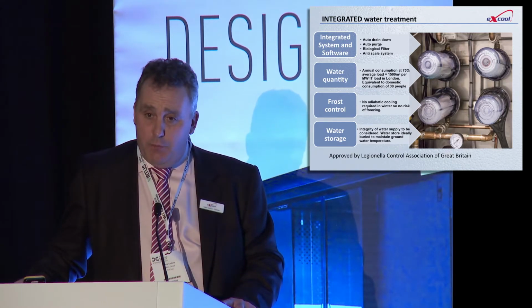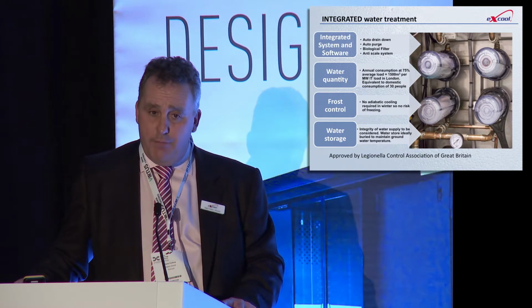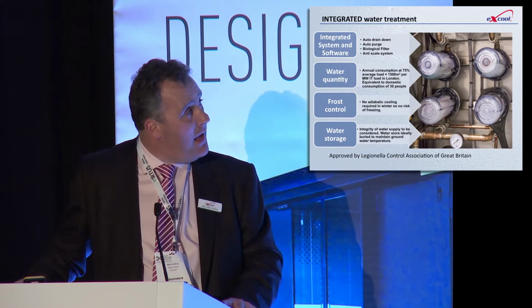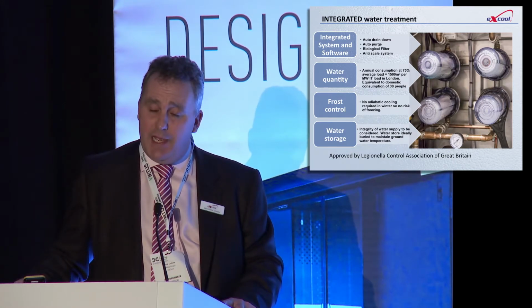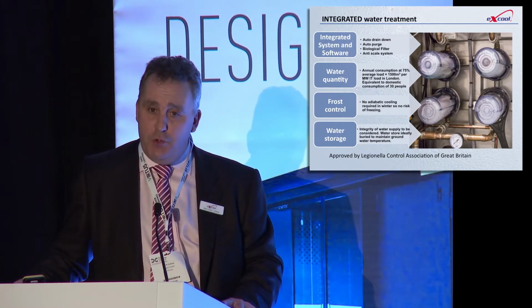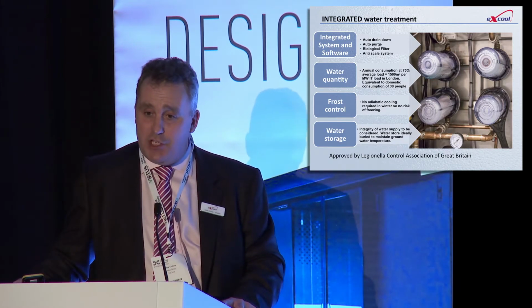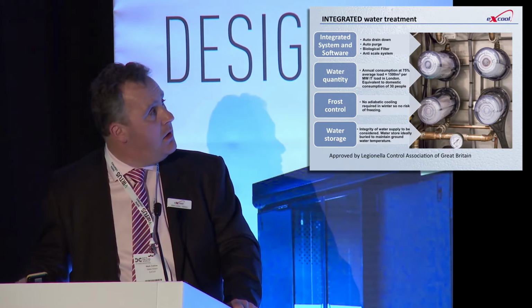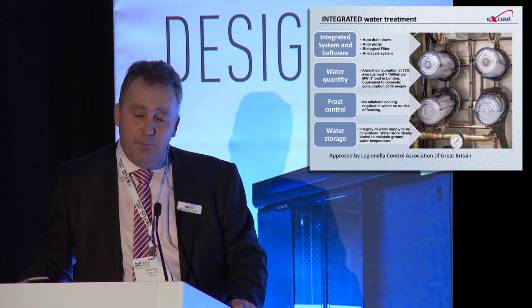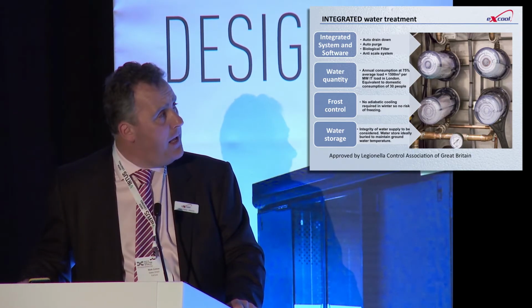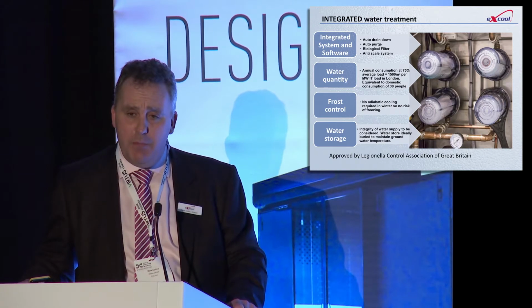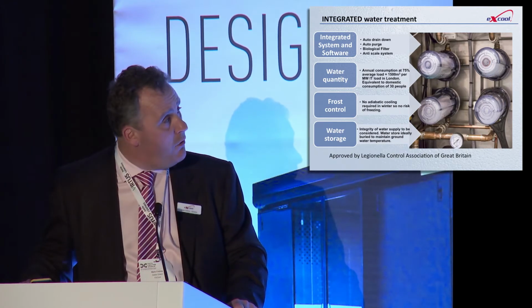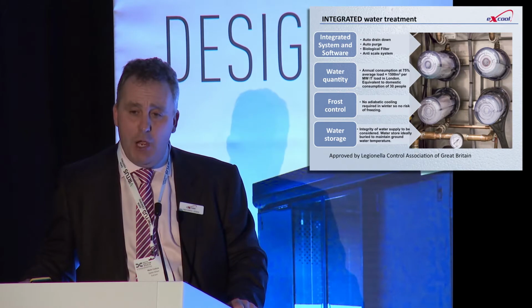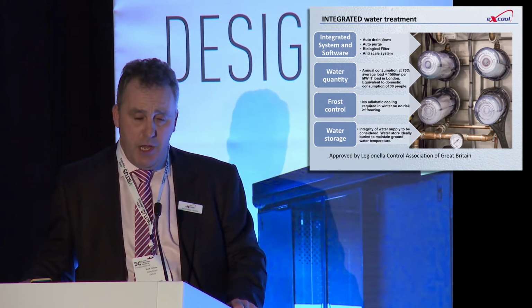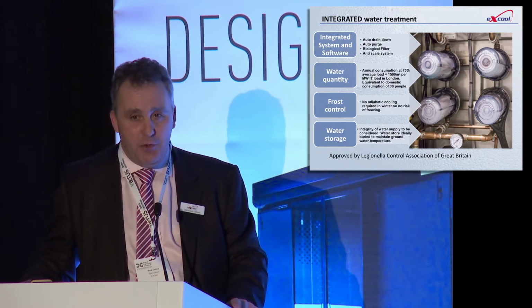We also have a biological filter built in, which is a 0.2 micron filter, which will filter out bacteria, which is 0.6 micron. And we have an anti-scale system, which prevents scale building up within the unit, which is a food source for bacteria, but is also quite detrimental to the performance of the unit. In terms of water quantity, it's fairly small as well. We're only using around 1,500 cubic meters per annum, which is the equivalent of around 30 people's domestic use per megawatt of cooling. In terms of process cooling, it's a drop in the ocean, excuse the pun.